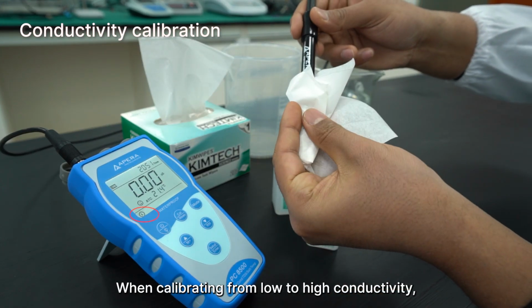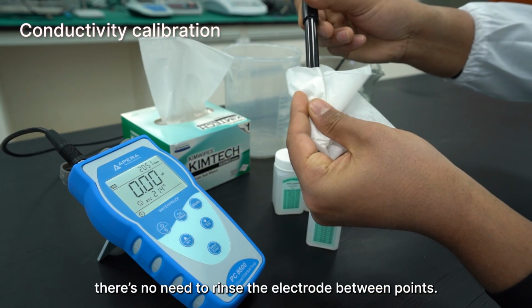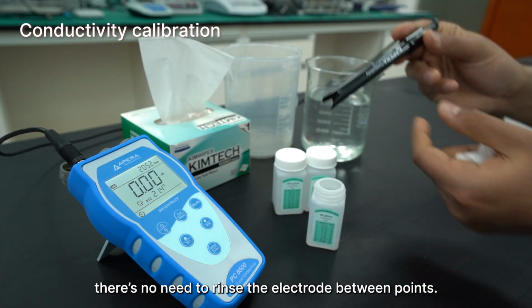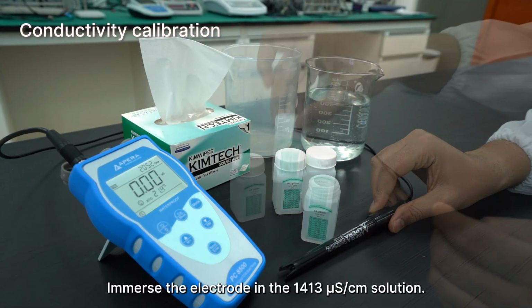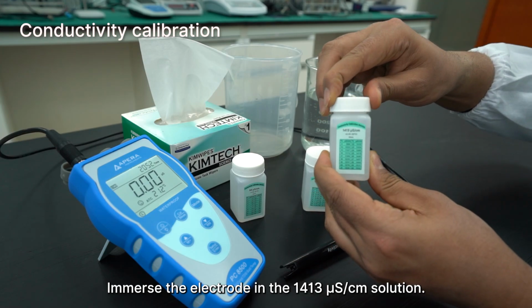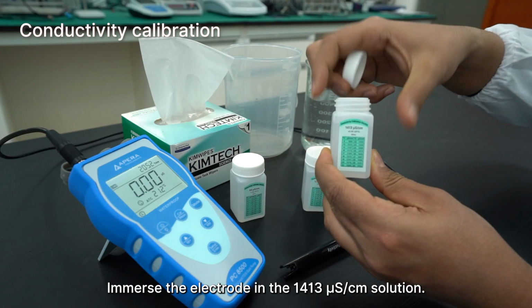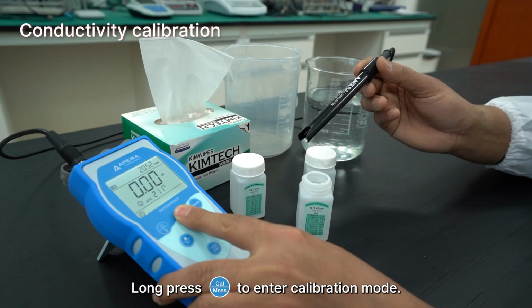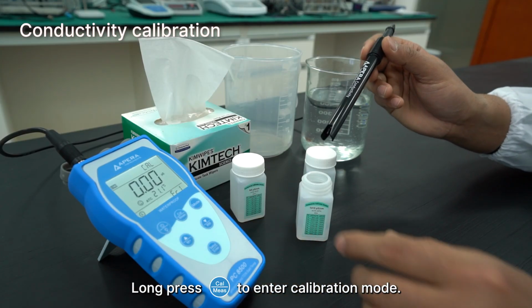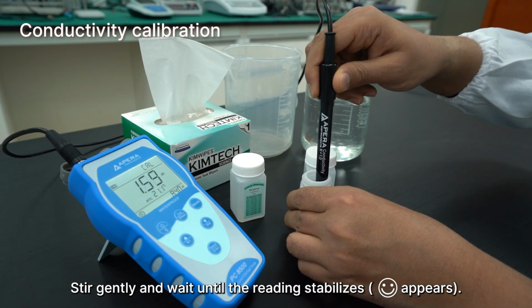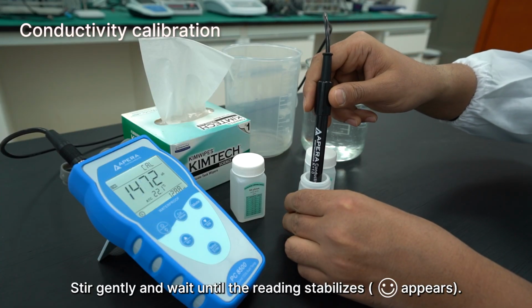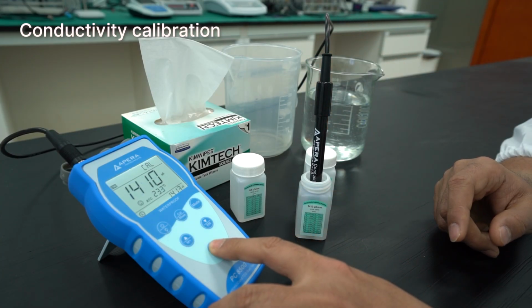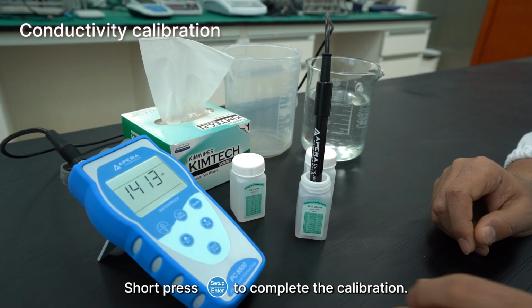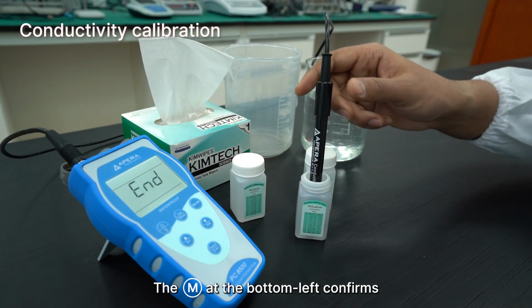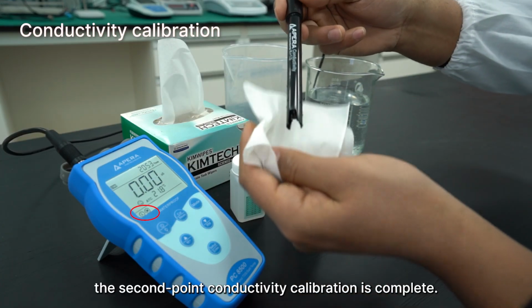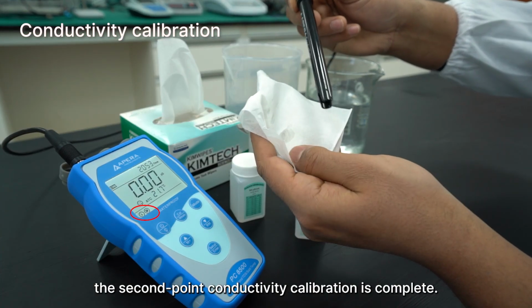When calibrating from low to high conductivity, there's no need to rinse the electrode between points. Gently wipe it dry with a Kim wipe. Immerse the electrode in the 1413 microsiemens per centimeter solution. Long press the cal button to enter calibration mode. Stir gently and wait until the reading stabilizes. Short press enter to complete the calibration. The smiley icon at the bottom left confirms the second point conductivity calibration is complete.